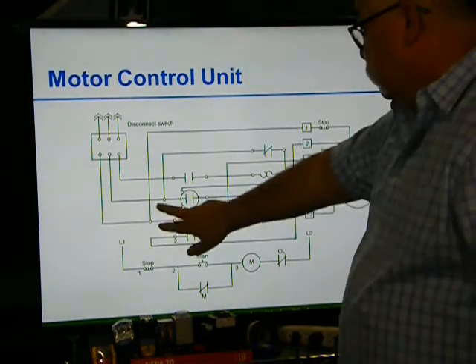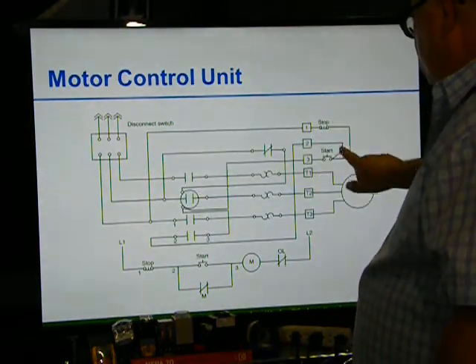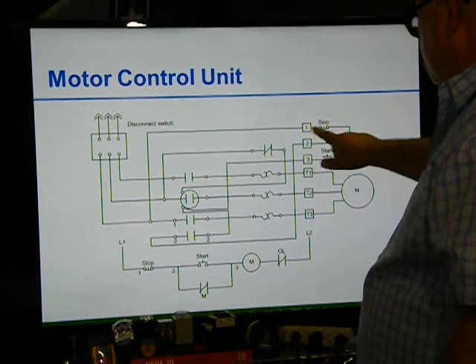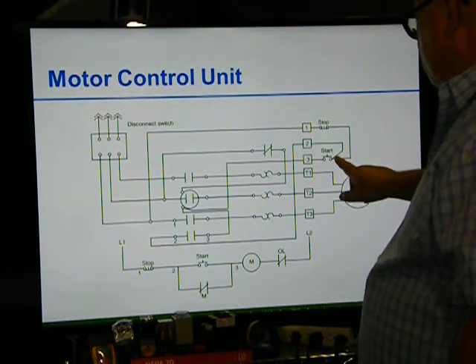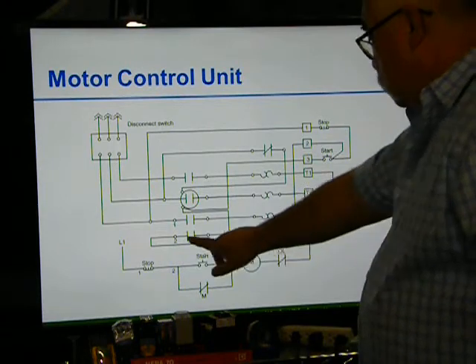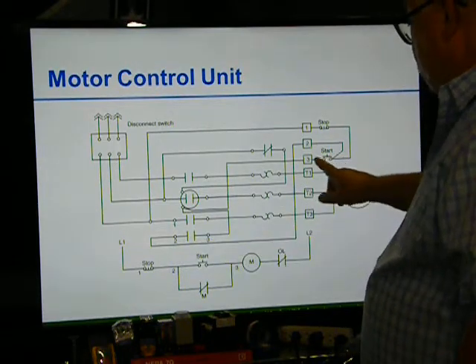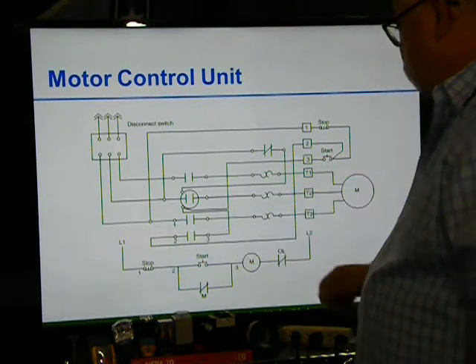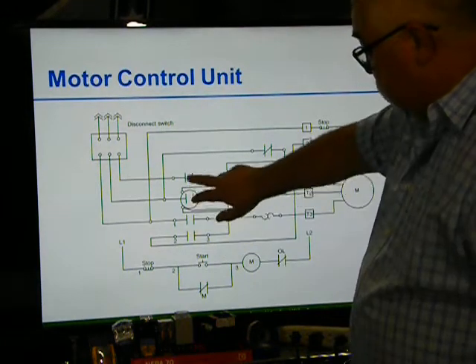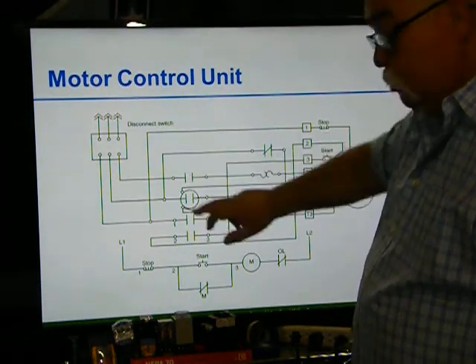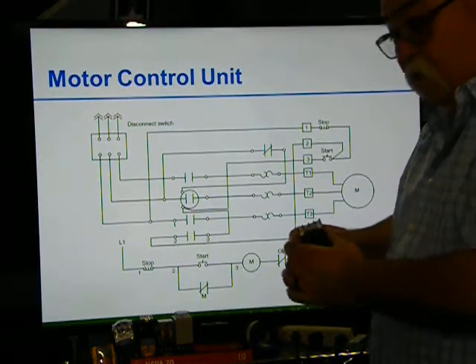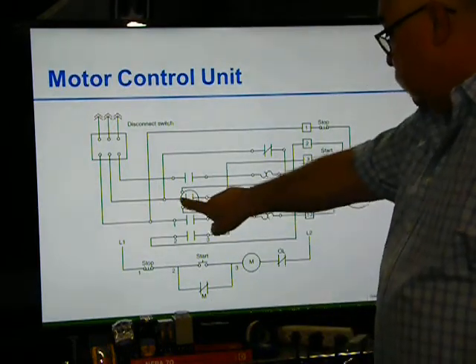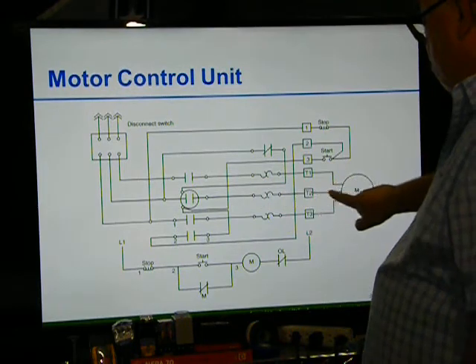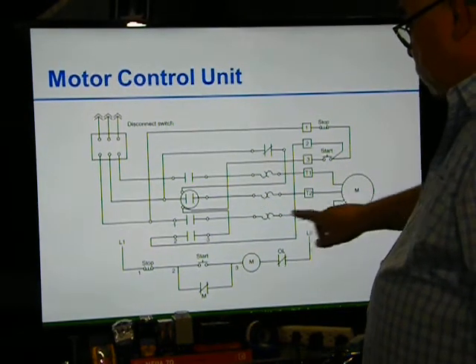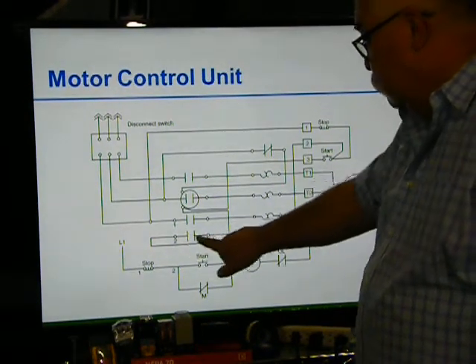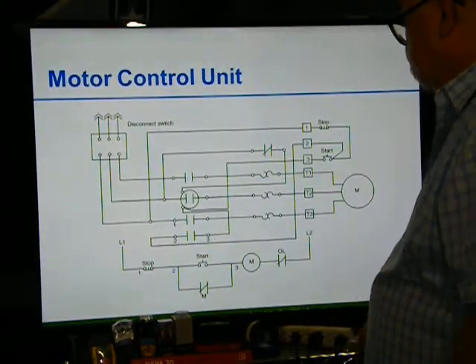Okay, so here it comes off. They're bringing in our power. They're doing the stop starts. So here's the stop, going to the start, 2, going to the contactor, and then here's going to the other side of the auxiliary. These 3 here are our contacts inside of here for the power. When this contact closes, power comes down, goes through the overload, and goes through the motor. This here is my auxiliary, the 2 and the 3 here.